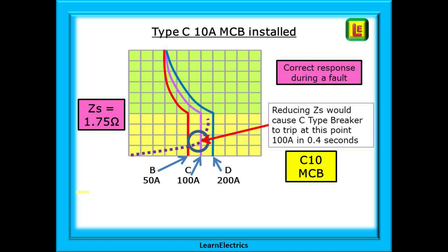Of course, in real life, it is often difficult to reduce the ZS, so we must check this first before changing types. But you never know, you might be lucky, the actual ZS might already be less than 1.75 ohms.